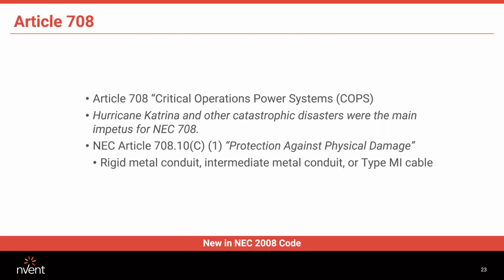Okay, you heard me mention before Article 708, Critical Operations Power Systems, otherwise known as COPS. This was brought about as a result of Hurricane Katrina. That was the main driver behind this. And it's basically stating that if you have any building that's going to be used as a command center in the event of a local or national emergency, every feeder in that building not only must be fire rated for 2 hours, but also needs to be protected against physical damage. This is not only emergency feeders, but normal feeders as well.